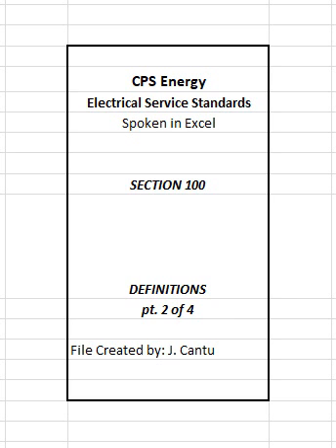Grounded. Connected to or in contact with earth or connected to some extended conductive body that serves instead of the earth. Grounded conductor. A system or circuit conductor that is intentionally grounded. Grounded effectively. Intentionally connected to earth through a ground connection or connections of sufficiently low impedance and having sufficient current carrying capacity to limit the buildup of voltages to levels below that which may result in undue hazard to persons or to connected equipment. Grounding conductor.